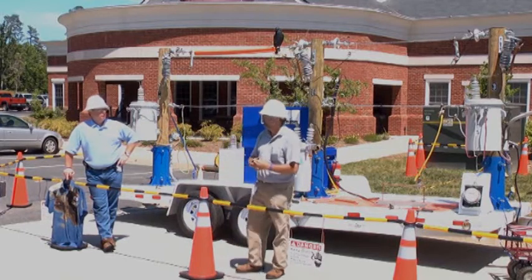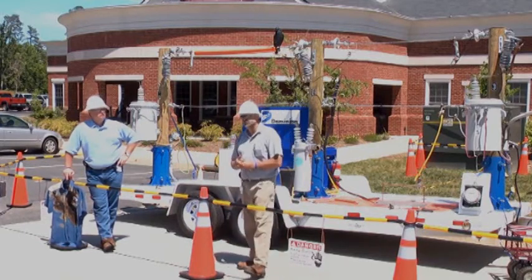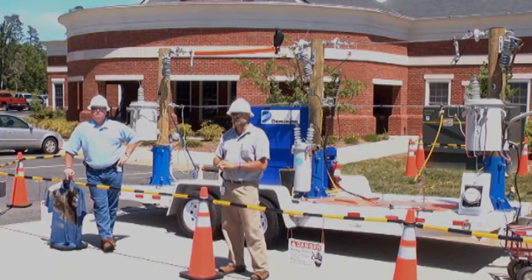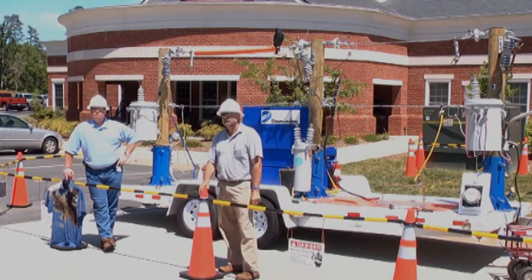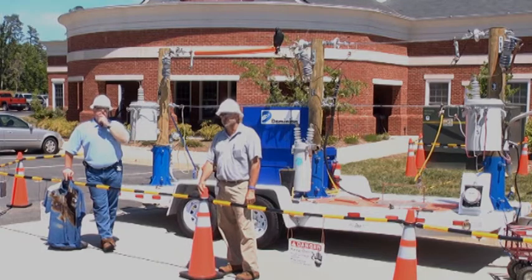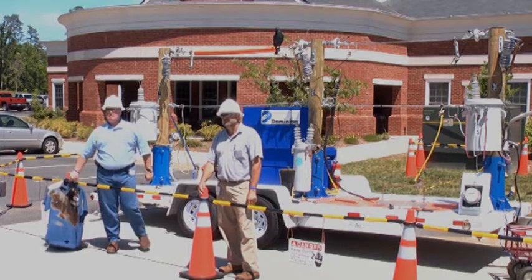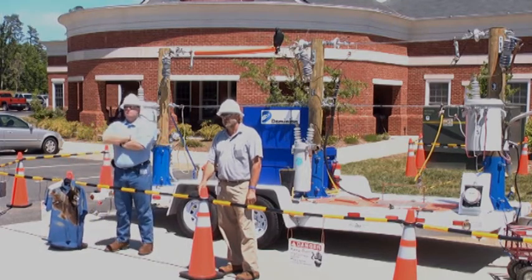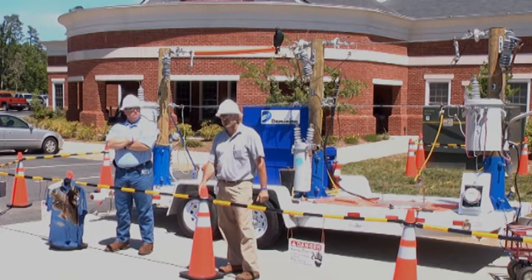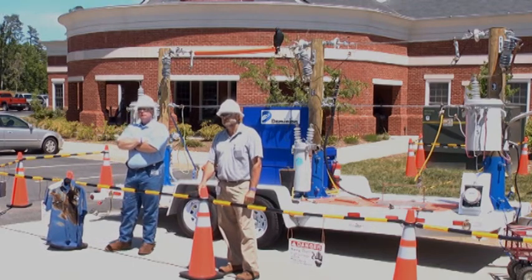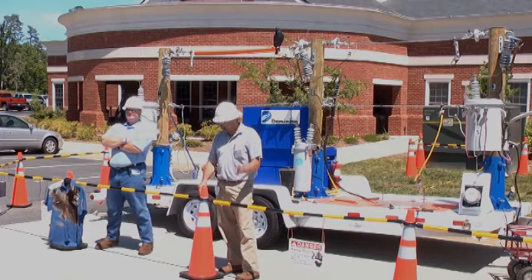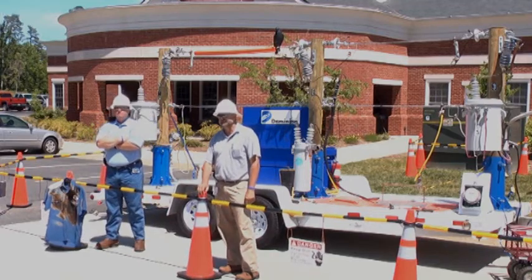Explain what the customer would see on their side. They would see partial lights. A lot of your commercial motors, like air handling units, anything that's three phase, you'll start seeing motors and ballasts running up. That's their choice if they put protection on them or not. In this case, they didn't. Well, not a case, that was their choice.